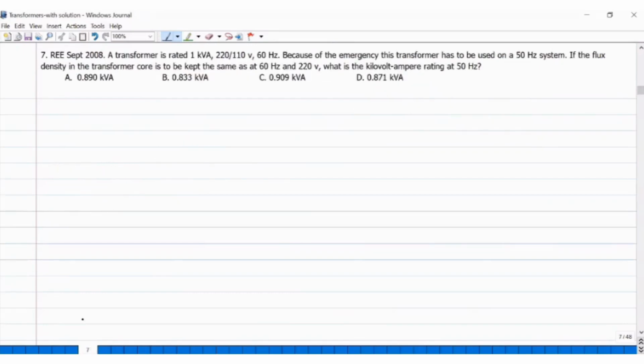Okay, number 7: a transformer is rated 1 kVA, 220 by 110, 60 Hz. Parang binigay din ata to. Because of the emergency, this transformer has to be used on a 50 Hz system if the flux density in the transformer core is to be kept the same as at 60 Hz and 220 volts. So what is the kilovolt ampere rating at 50 Hz?